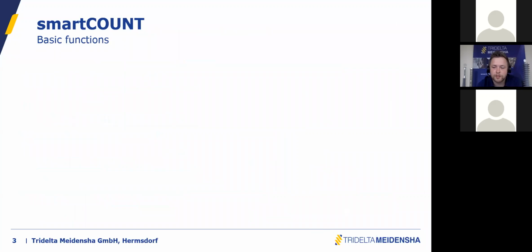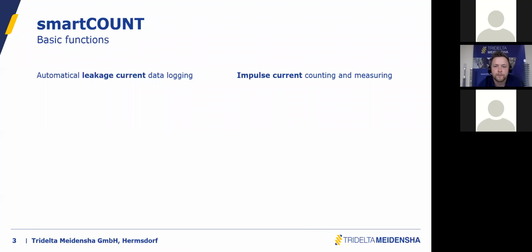When we talk about surge arrestor monitoring, normally 2 basic functions are required to make a health assessment on a surge arrestor. At first, this is leakage current monitoring, and for the smartCOUNT, we speak precisely about automatic leakage current data logging, which is important to receive something like a leakage current trend. And on the other hand, of course, impulse counting has been and is still used to do some health assessment on the surge arrestor. More or less, it's useful if you understand the behavior, maybe together with the leakage current, then this is an important point as well.